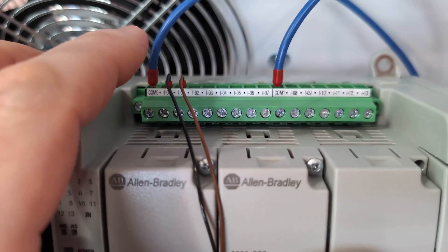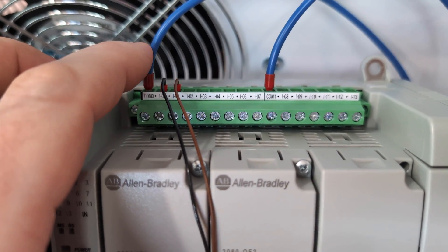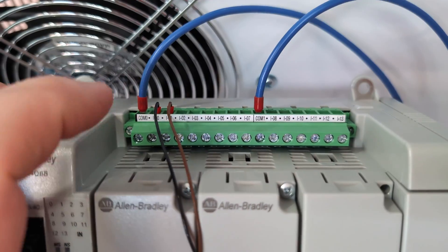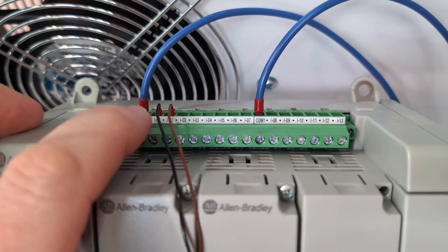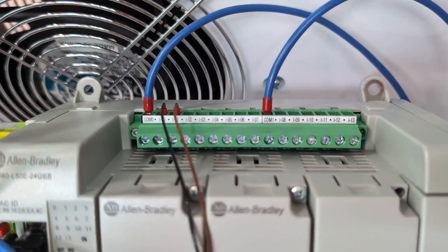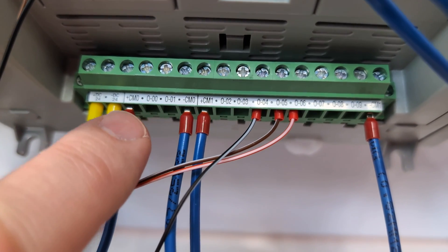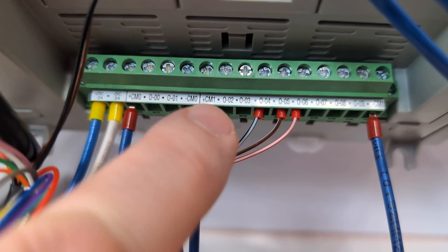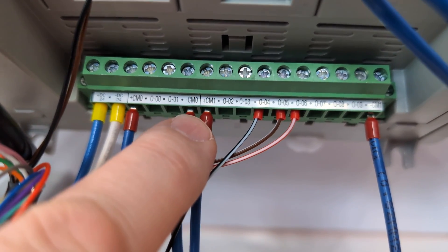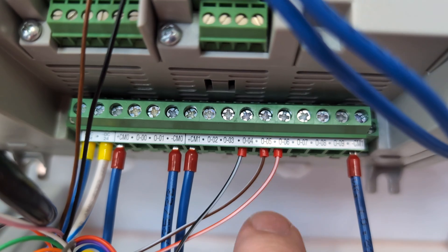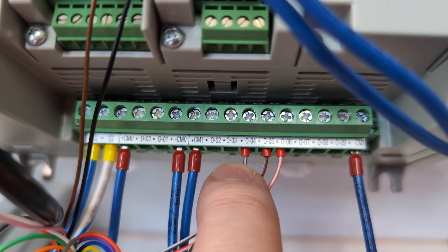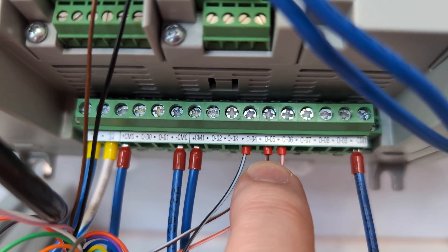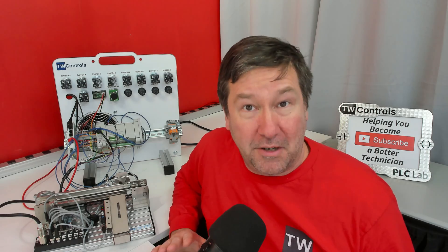At this point, you should have 0 volt on the right set of terminals on both COM 0 on the top and COM 1. And then we have pin 1 of our 15 pin connector going to input 0, pin 2 going to input 1. And on the bottom, we have plus 24 volt going to plus CM 0 and plus CM 1. We have 0 volt going to minus CM 0, minus CM 1. And then our three outputs are going to be output 4 on pin 2, output 5 on pin 4, and output 6 on pin 6.